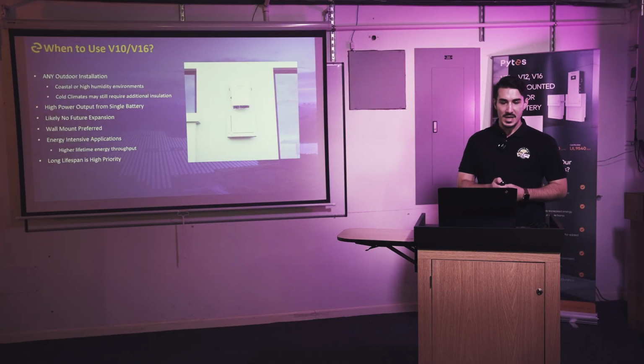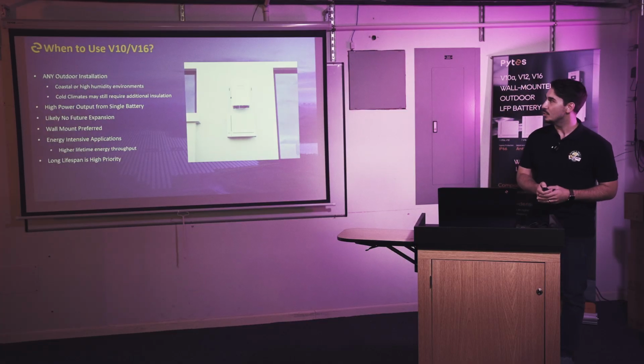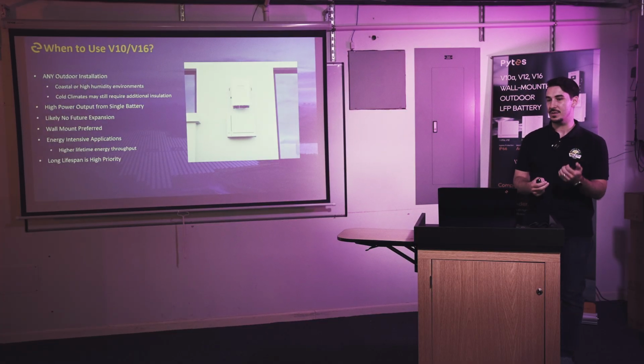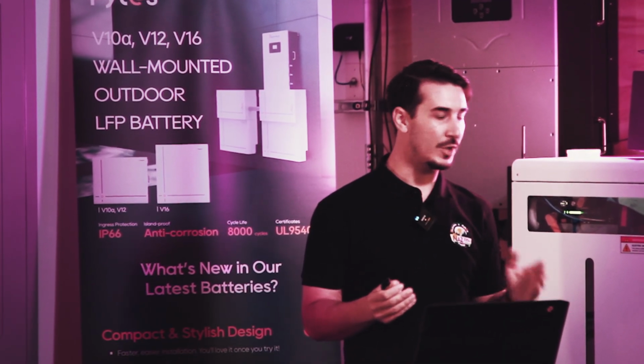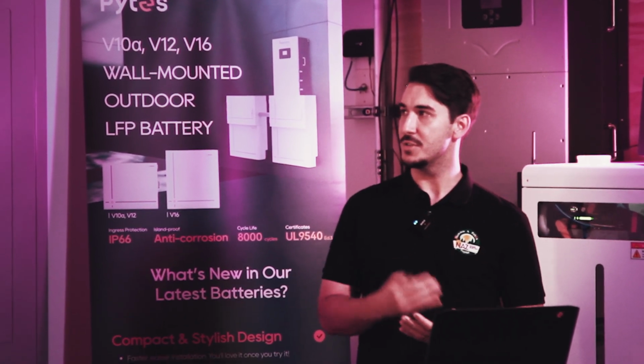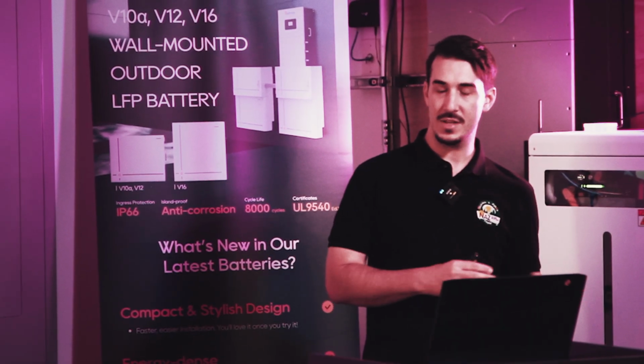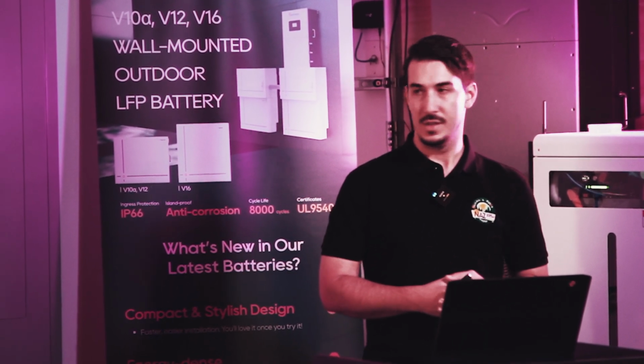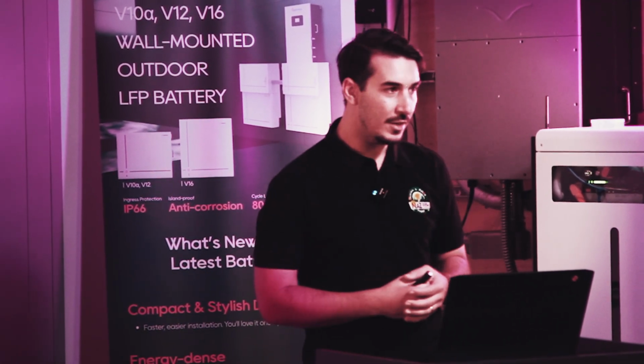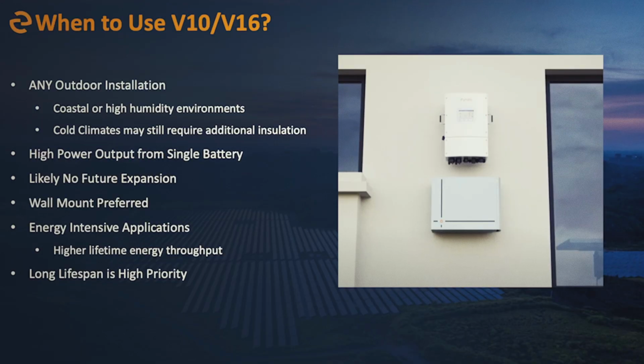I guess for me, when I first studied these two new products, my biggest question is: when do you use these? Because we've introduced now 4 or 5 different low voltage solutions. For me, any outdoor installation, look at V10 or V16, especially if it's coastal, especially if it's humid, or cold climates to an extent - we talked about some of the temperature limitations. If you're doing a project in northern Canada, you can't just stick this on the wall and expect the little heaters to keep up - you'll have to do something extra to keep the battery at the right temp. If somebody's looking for a single battery install and a single inverter install but wants very high power output from that one battery, these are good options as well. This one is a bit interesting for me.